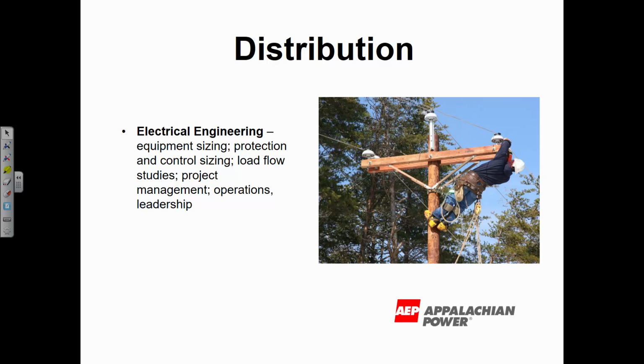However, in rural areas, I might have circuits with 300 miles of line on them. There are a couple circuits in rural parts of West Virginia that literally have 300 miles of line. So you have to have not only the station breaker, but also line reclosers, which are basically breakers hung on the poles. You have to have fusing and all sorts of other things.